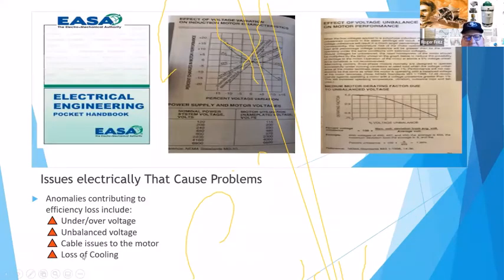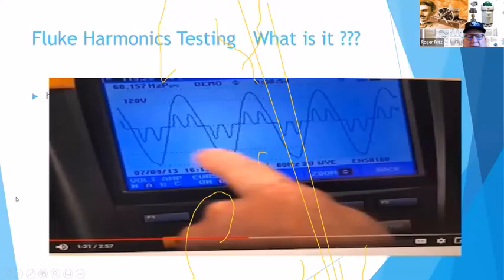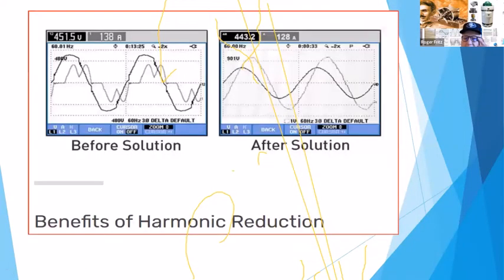Again, the cable issues. The other is loss of cooling on a motor. So a submersible motor running in cold water application really doesn't have quite that much effect, but it is a factor when you're looking at a horizontal or vertical motor, that if you lose that cooling from dirt, dust, debris, it again goes back and affects those coils that are inside the motor that end up getting an opportunity for failure.